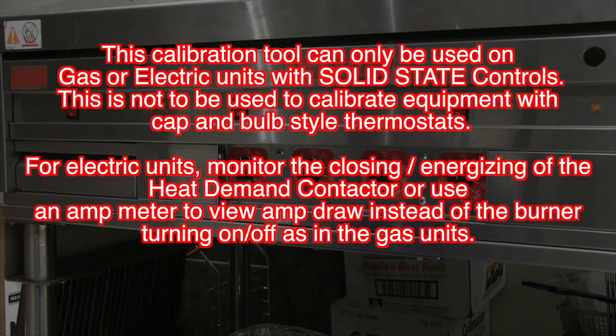This calibration tool can only be used on gas or electric units with solid-state controls. This is not to be used to calibrate any piece of equipment with a cap and bulb style thermostat. For electric units, monitor the closing or energizing of the heat demand contactor, or use an amp meter to view the amp draw instead of the burners turning on and off as with the gas units.